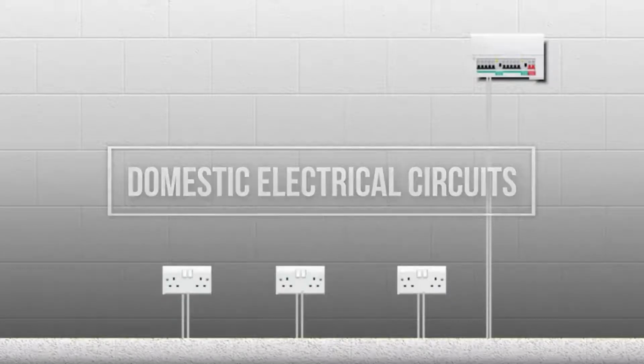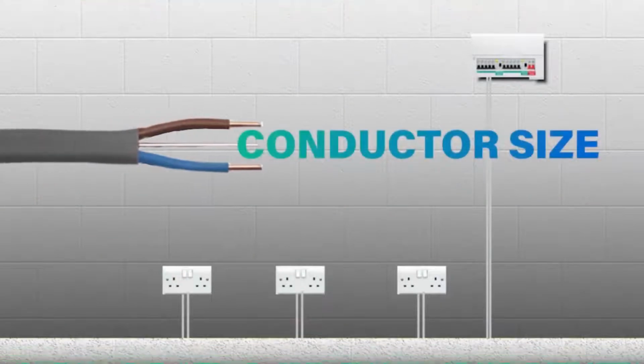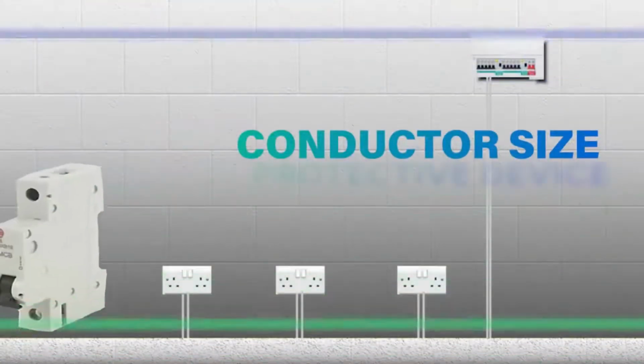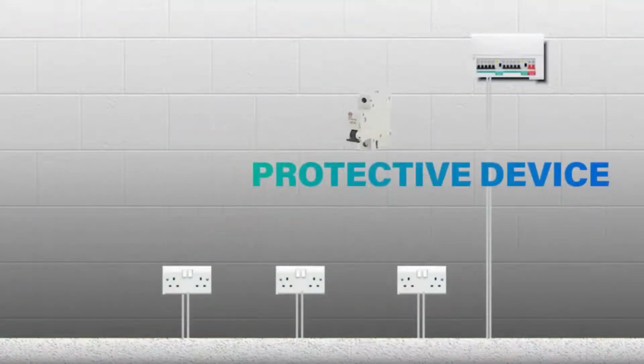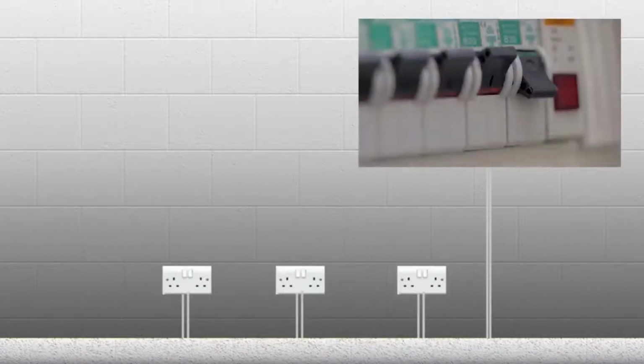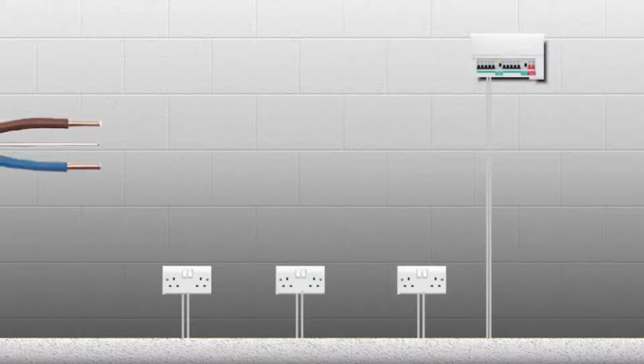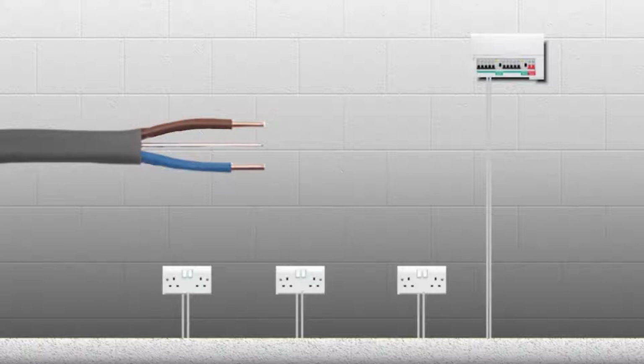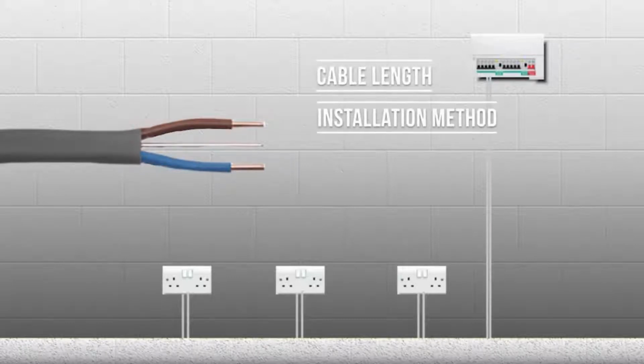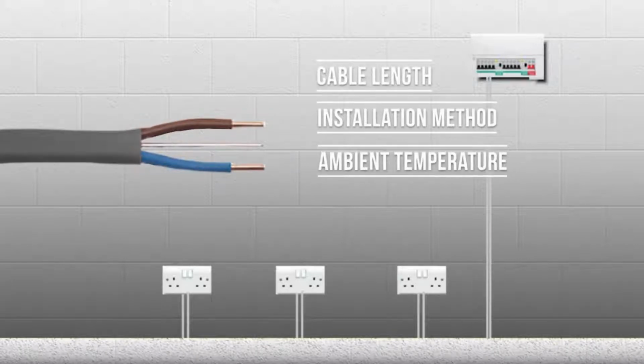Domestic electrical circuits, the size of conductors that are used in the circuits, as well as the size or rating of protective device. Every new circuit has to be designed by calculating the maximum load of the circuit, choosing the right size circuit breaker, and calculating the right size of the cable, by taking into account its length, method of installation, ambient temperature, voltage drop, and few other factors, and then the whole circuit should be tested. I'm not going to do any of these calculations in this video.